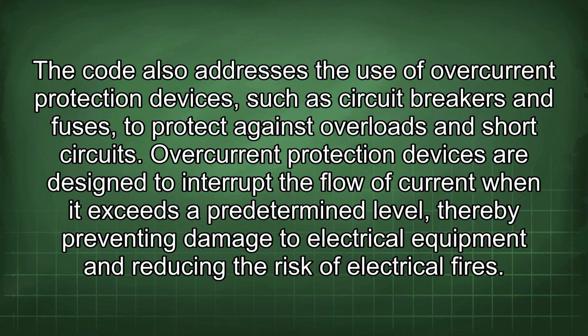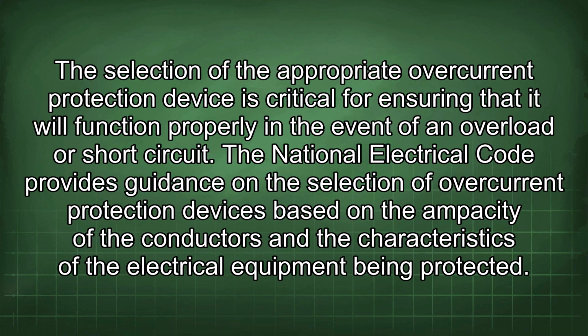The code also addresses the use of overcurrent protection devices such as circuit breakers and fuses to protect against overloads and short circuits. Overcurrent protection devices are designed to interrupt the flow of current when it exceeds a predetermined level, thereby preventing damage to electrical equipment and reducing the risk of electrical fires. The selection of the appropriate overcurrent protection device is critical for ensuring that it will function properly in the event of an overload or short circuit. The National Electrical Code provides guidance on the selection of overcurrent protection devices based on the ampacity of the conductors and the characteristics of the electrical equipment being protected.